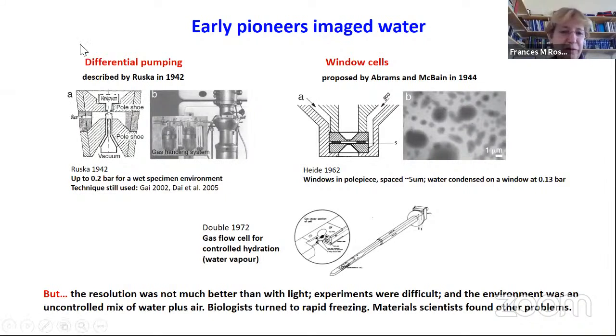In one of them, we have differential pumping. The sample is in one part of the microscope column. The pressure there is quite high because it's got water and it's evaporating. It needs to be at equilibrium in an atmosphere of water vapor, and so you have differential pumping with small apertures and pumps on the other side that make sure that the rest of the microscope is under vacuum. So the electrons pass through the column, they pass through some region of poor vacuum, and then the rest of it is okay, and that's fine. You can get decent images. This is a technique now called open cell electron microscopy.